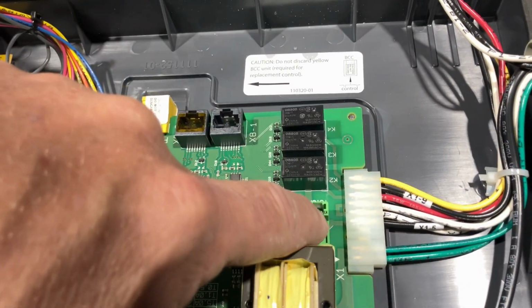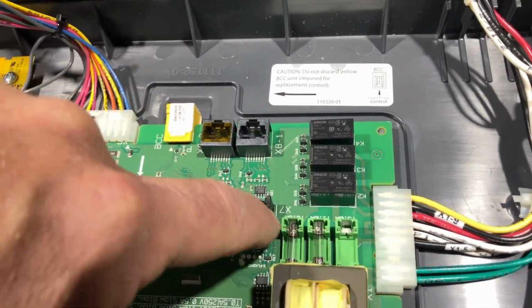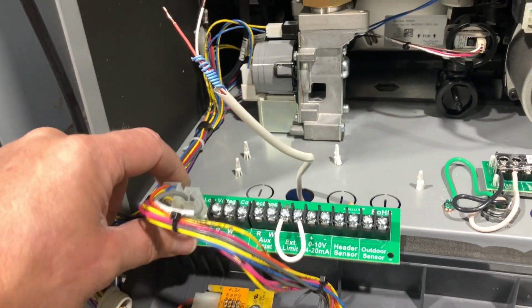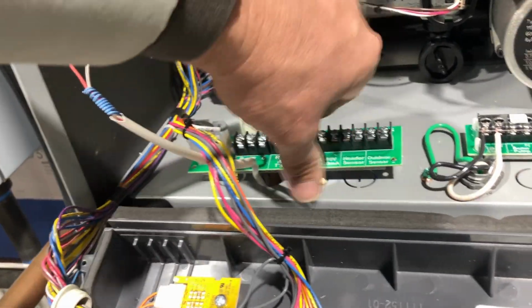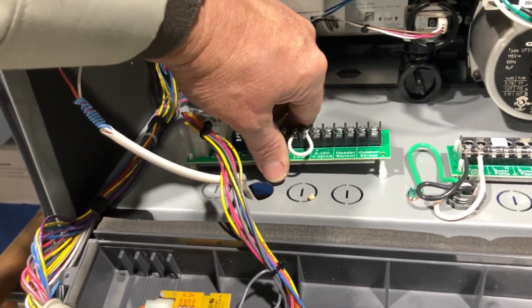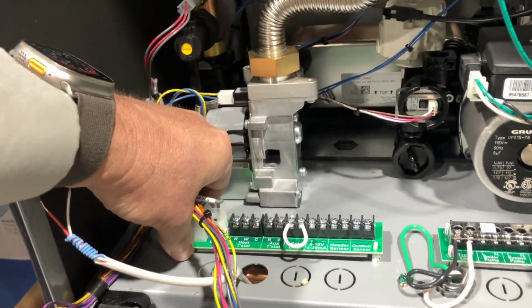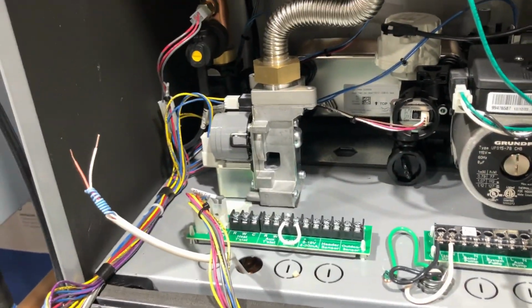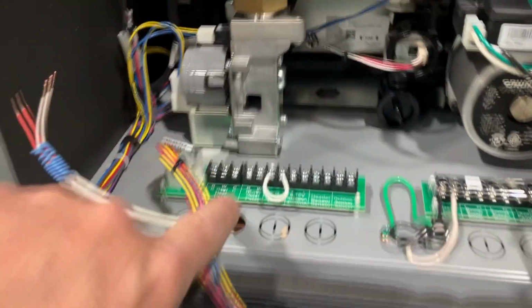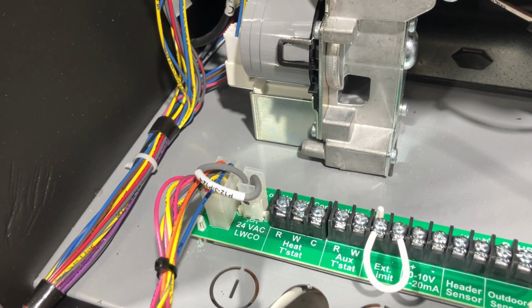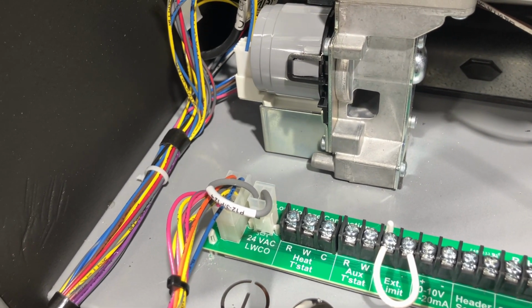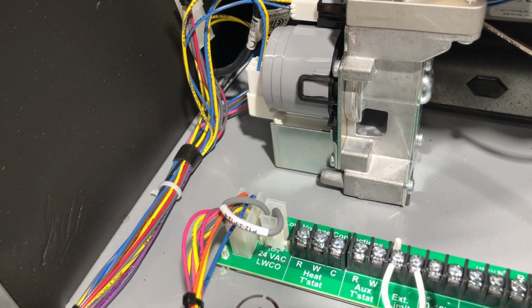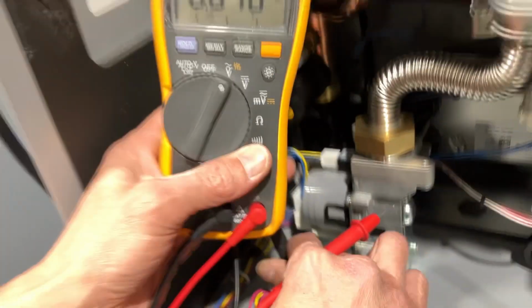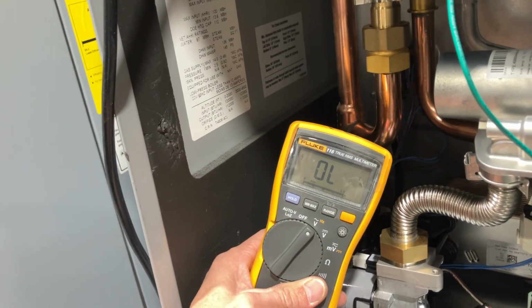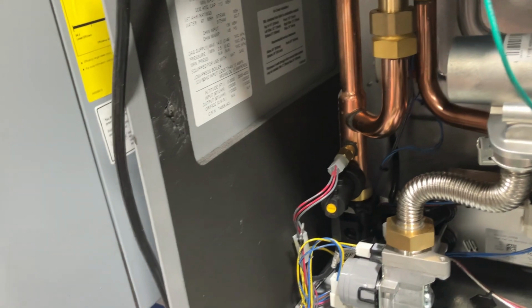For testing purposes, I took that fuse holder from there, I put it there. Now we have voltage between R and W. We're going to put this back on there. We pulled this to inspect it. Everything's fine. We're going to turn our power back on. And now we're going to show you guys on camera, 24 volts on R and W. Perfect, and we have our voltage there.